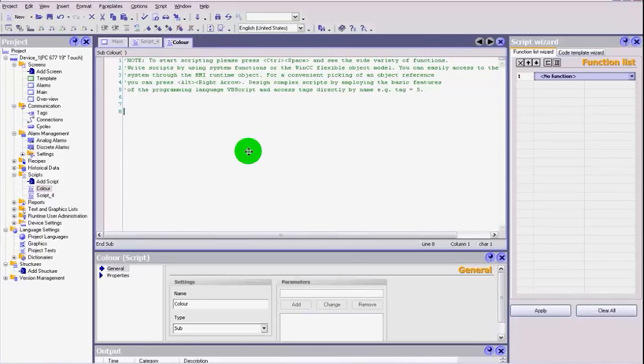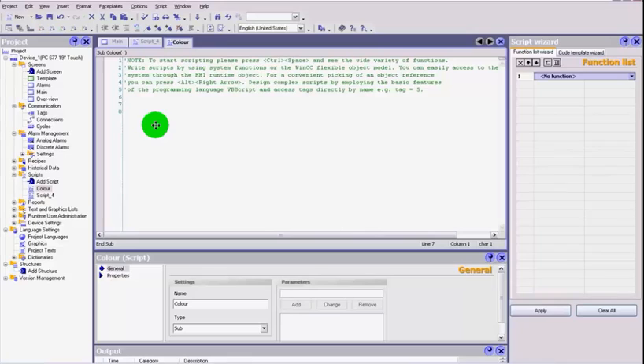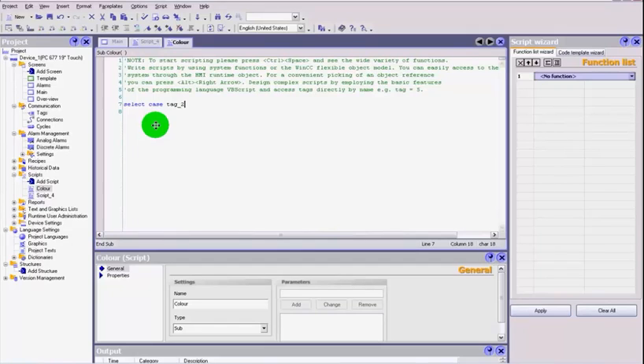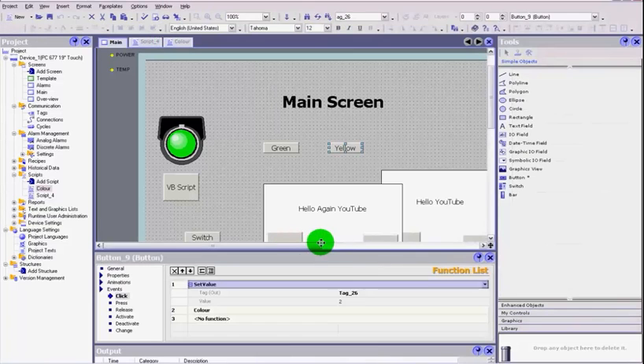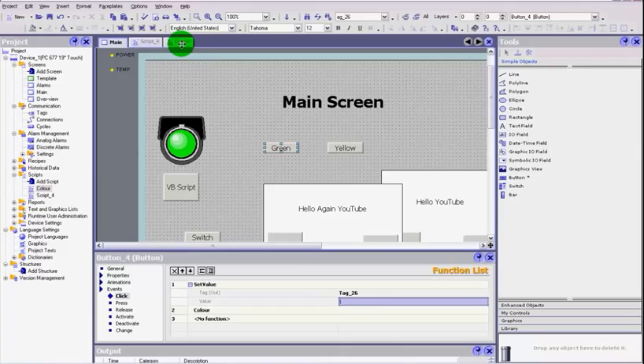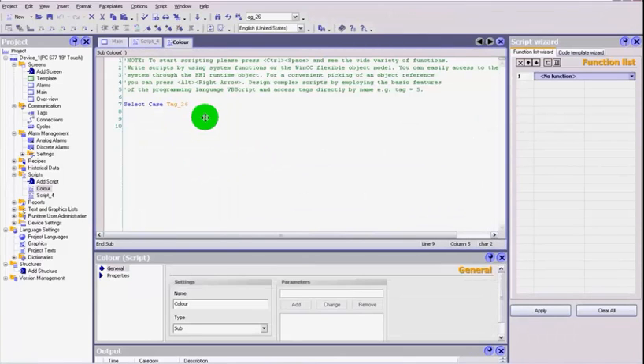So let's go to our script now. I'm going to use a little select case command, which is a standard VB. We're going to use this VB script and we're going to use select case. So the command in VB is select case, and remember our tag value which was tag_26. So now we have got a value that we're sending into the script which is tag_26, and that is going to be a value of two or one.